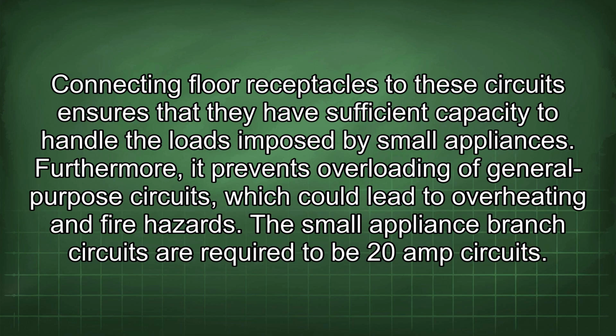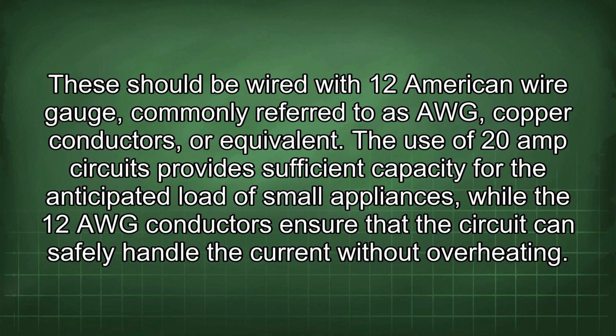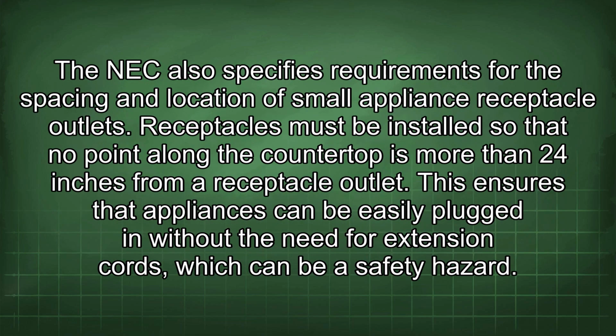The small appliance branch circuits are required to be 20-amp circuits. These should be wired with 12 American Wire Gauge, commonly referred to as AWG, copper conductors, or equivalent. The use of 20-amp circuits provides sufficient capacity for the anticipated load of small appliances, while the 12 AWG conductors ensure that the circuit can safely handle the current without overheating. The NEC also specifies requirements for the spacing and location of small appliance receptacle outlets. Receptacles must be installed so that no point along the countertop is more than 24 inches from a receptacle outlet. This ensures that appliances can be easily plugged in without the need for extension cords, which can be a safety hazard.